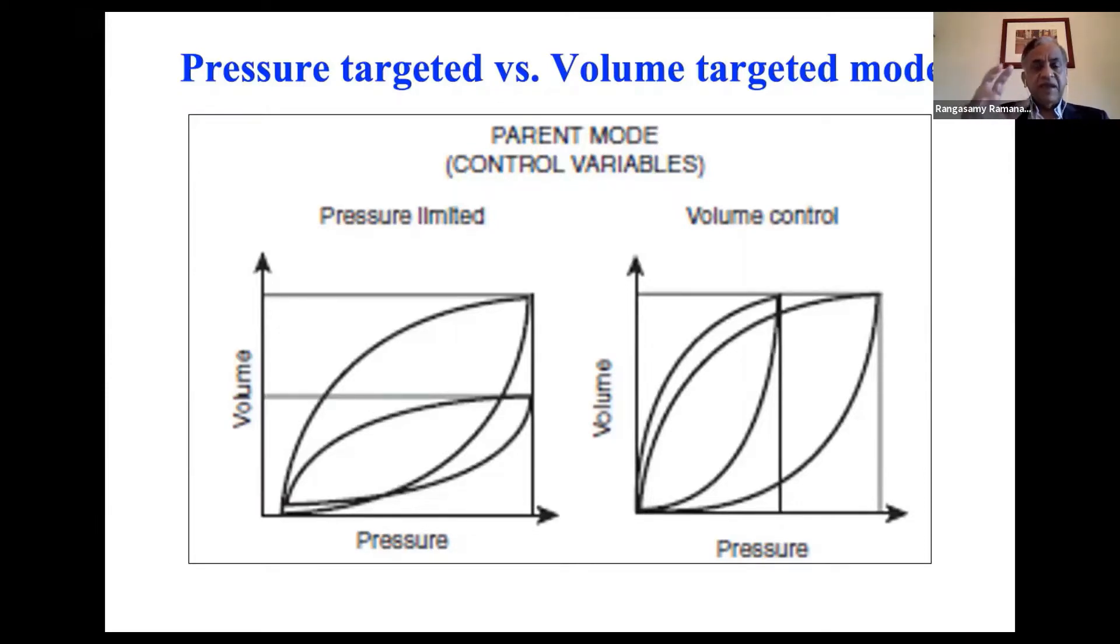But if you don't have the ventilator that can deliver a volume guarantee mode, you can still use pressure control. As long as you put a volume limit, you set the alarm on volume limit.